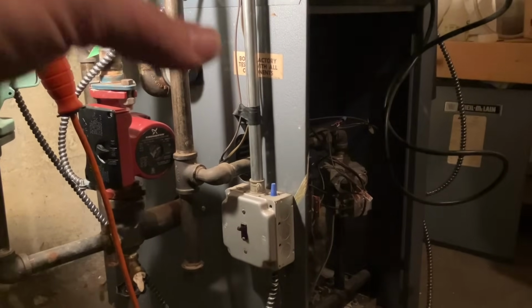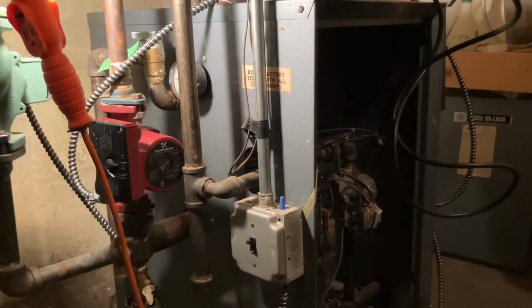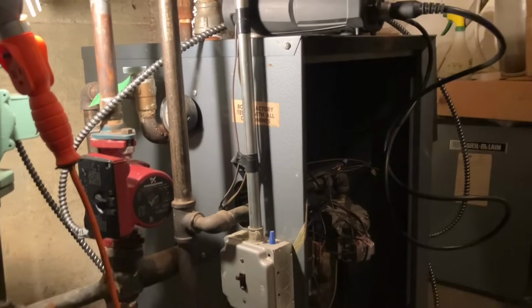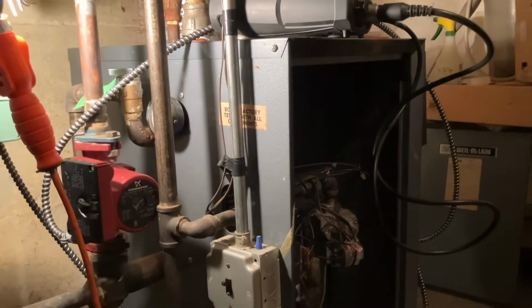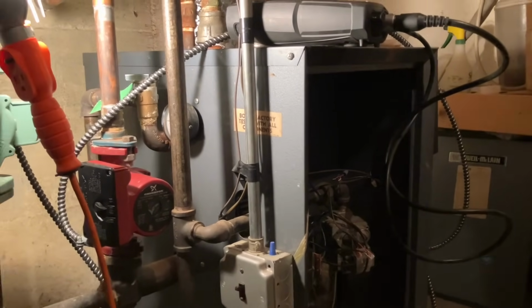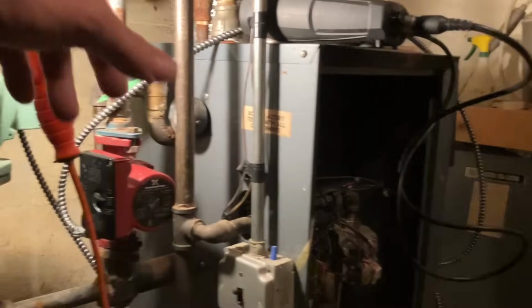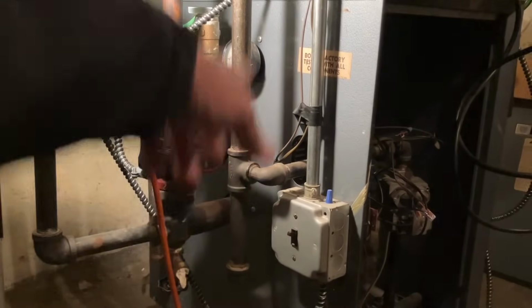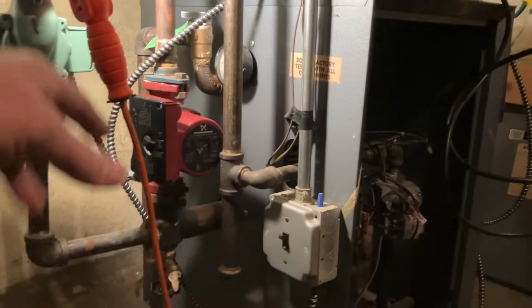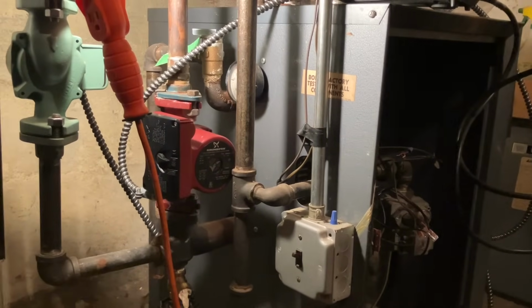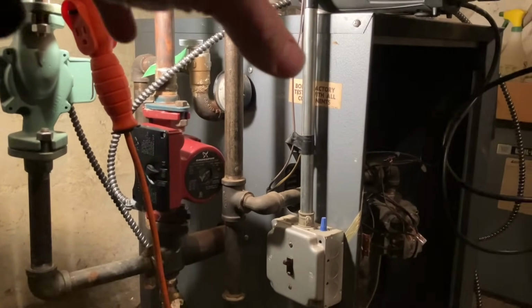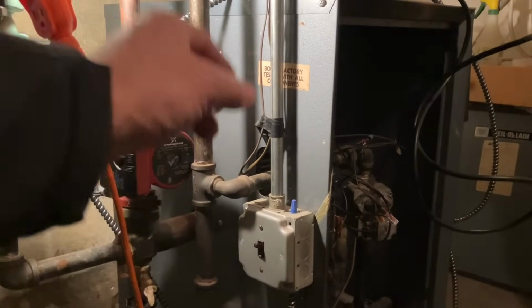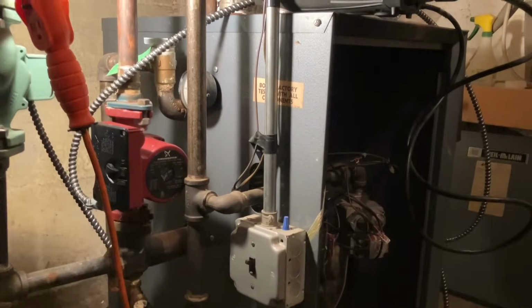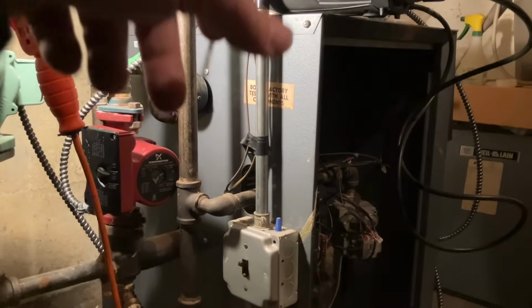You don't have a condensing boiler. You have a cast iron boiler that wants 180 degrees of heat. I can lower this to 165 and play it safe, but the lower I make this number, the lower my return temperature could be as it circulates back to the boiler. And if I go into dangerous territory at a certain threshold, when it gets too cold returning to the boiler, you'll shock the boiler and it'll condense at the boiler, which is cast iron, and you'll eat the boiler.